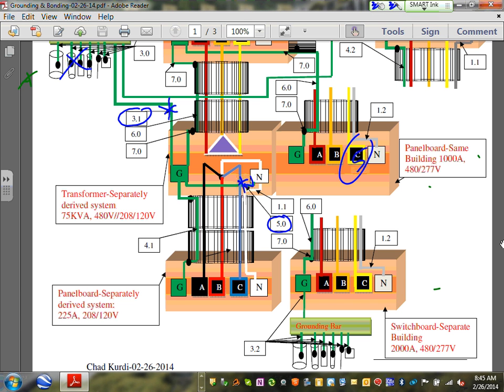Number 6, of course, another thing you have to do is the neutral. You have to create a neutral. Then you have to have something called 4.0. 4.0, this is called the supply side bonding jumper at the separately derived system. Supply side bonding jumper at the separately derived system. Okay, so that's what we're going to size and talk about one more time. I'm going to summarize them.